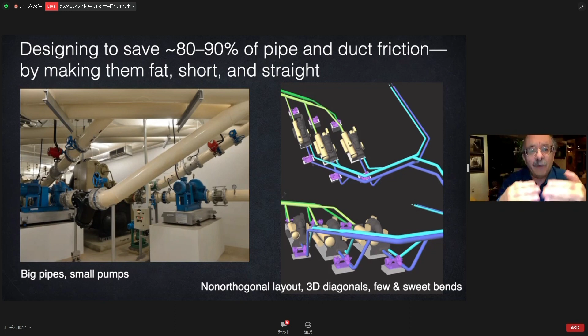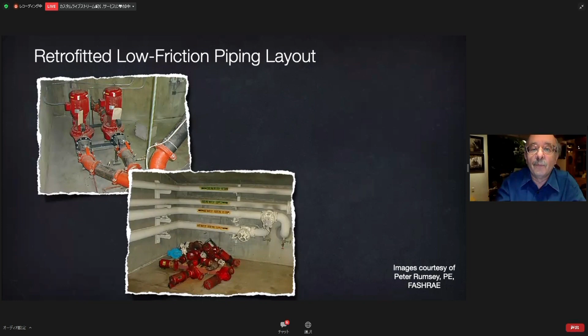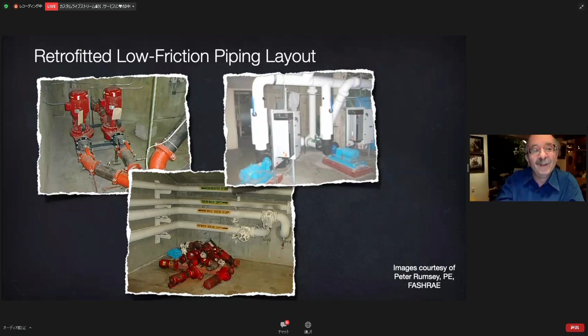That cut the pumping energy by 3/4 with a 2 or 3 month payback and eliminated 15 pumps that will never again waste energy and maintenance costs. Repiping another pumping loop and adding variable frequency drives doubled the flow and saved 85% of the energy. Peter simply asked the pipe fitters to lay out the supply pipes as if they were drains.